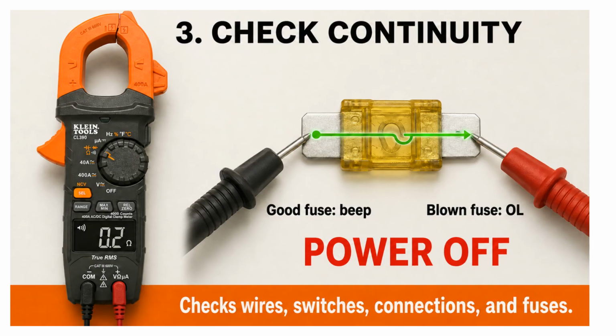Now place one probe on each end of the disconnected wire or fuse. If the meter beeps and shows a very low number, the path is complete. If the meter does not beep and shows OL, the path is open or broken. A fuse can look good and still be blown inside. Removing it and checking it with the meter is better than guessing by looking at it.